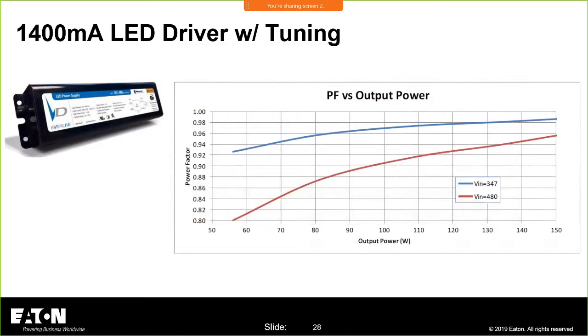And this is a 1400 milliamp LED driver that you would see in like a ballast replacement or whatnot that you would see in a lighting fixture, and you'll see that the power factor ranges anywhere from 0.8, so that if you're at 480 volts, from 0.8 up to 0.96, depending upon the output power of the solution. So I put this stuff in there simply because I just want to raise the awareness, and I never realized it.